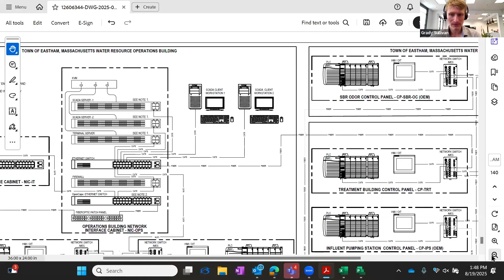The other thing in terms of redundancy, on a different note, is the network architecture as a whole. We have a ring topology, meaning all the PLCs on the network are set up like a ring. Lauren, if you can zoom out a bit, that might help with the visualization - but essentially from each PLC to the next, or each Ethernet switch, you can see it kind of goes in a loop. It's a little hard to read right now with the number of PLCs, but if you follow the lines between them, they go from the operations building up into the treatment building and then back around outside.